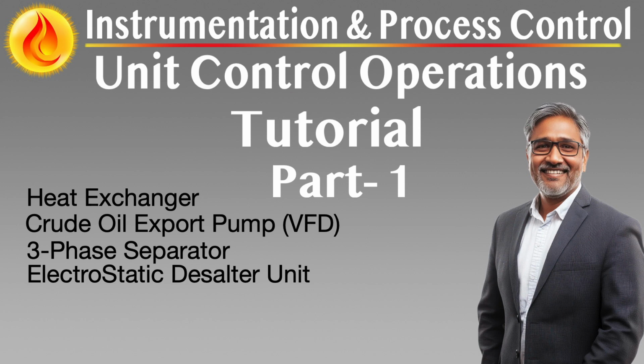Cyber-physical integration is a growing requirement. Separator controls are tied into safety instrumented systems, SIS, enabling interlocks based on overpressure, high levels, or gas detection. Emergency shutdown, ESD sequences are intelligently staged, e.g., gas blowdown may be delayed until oil levels drop to avoid re-entrainment or carryover. Alarms are also now more intelligent, using alarm shelving, prioritization, and time-stamped causality mapping to reduce nuisance alerts and improve operator focus during upsets.